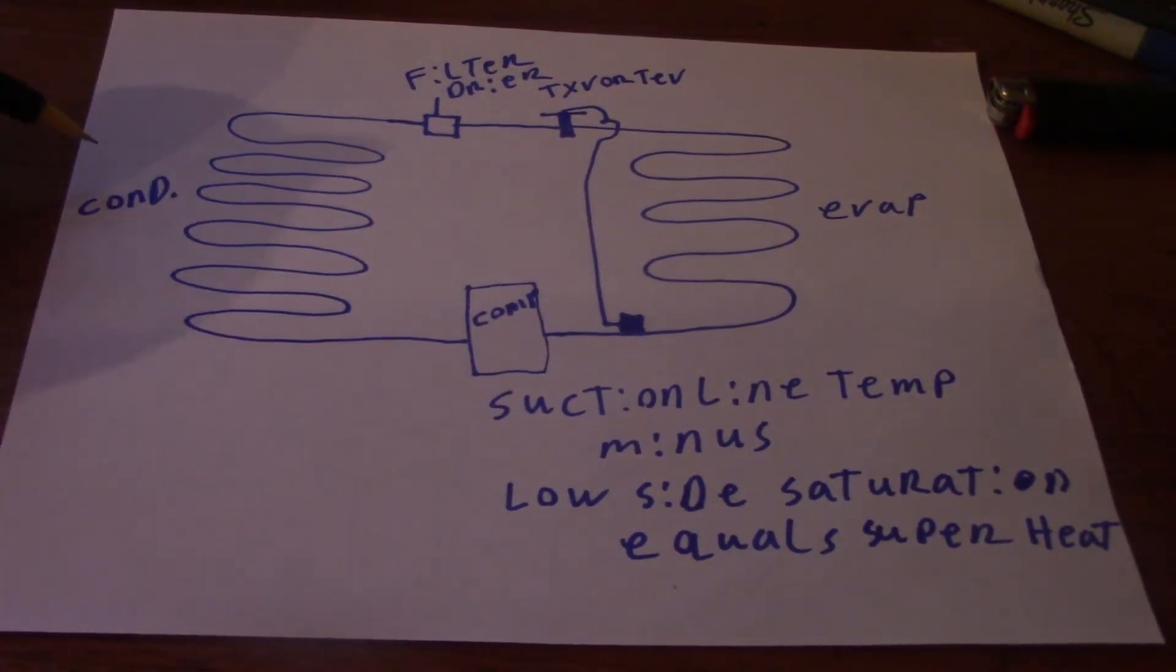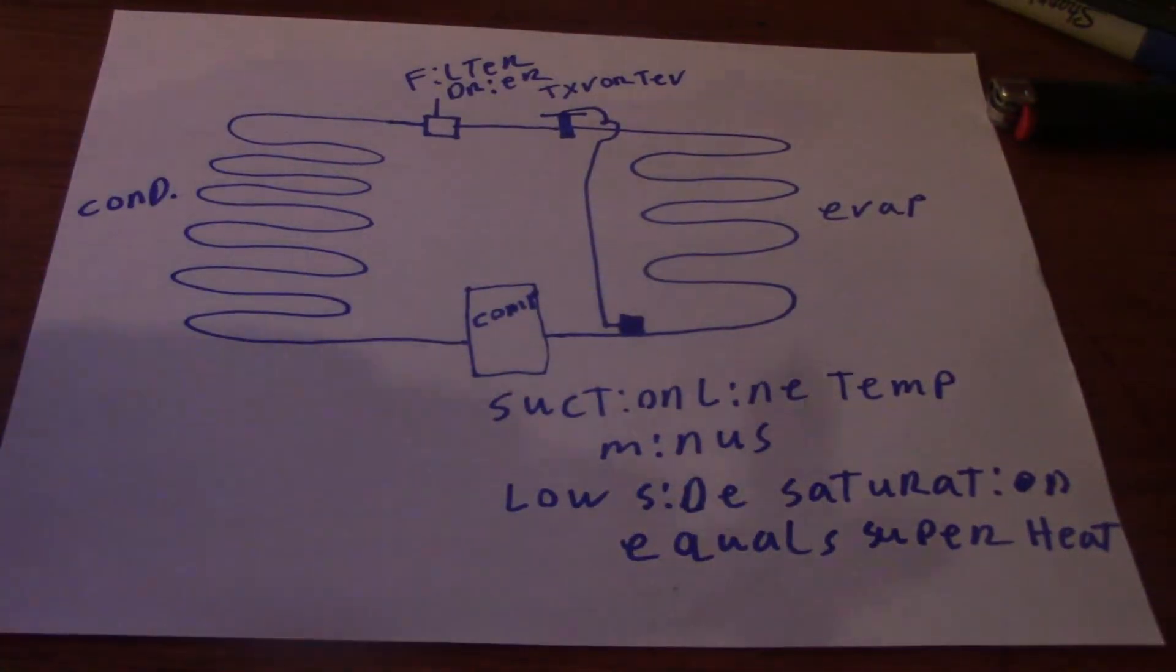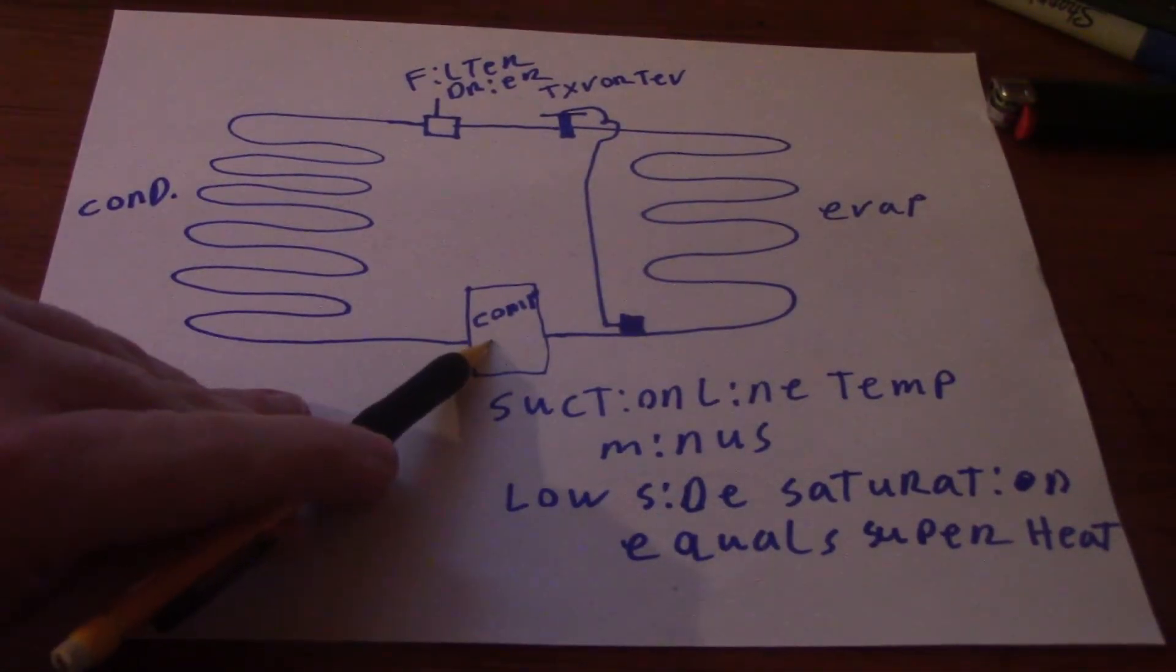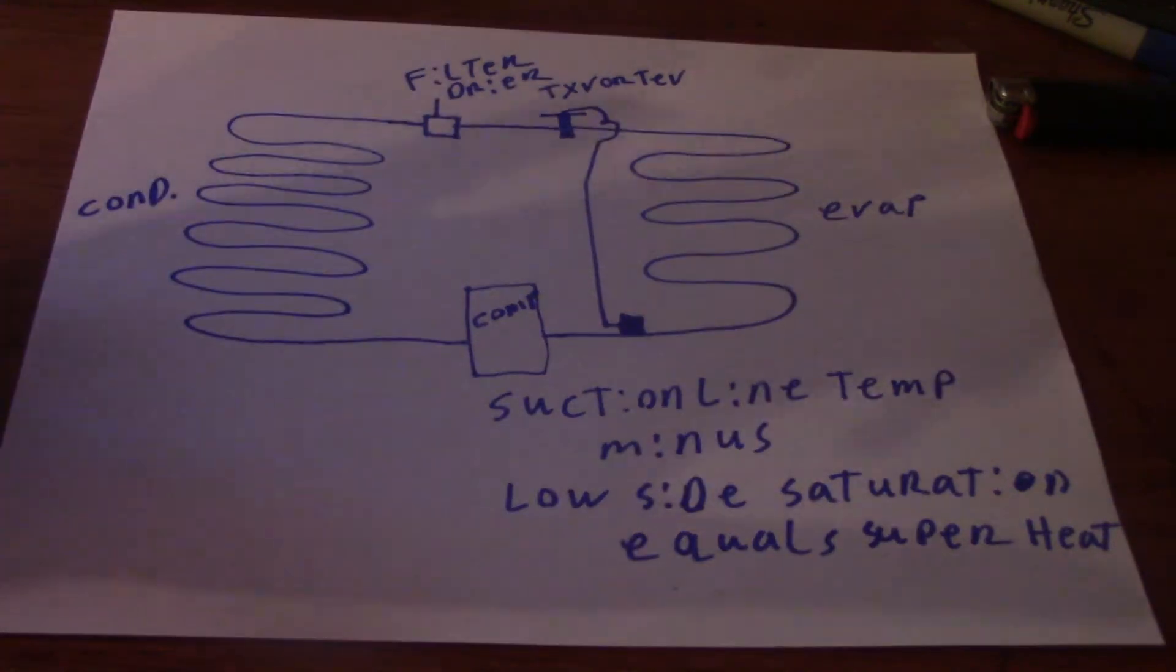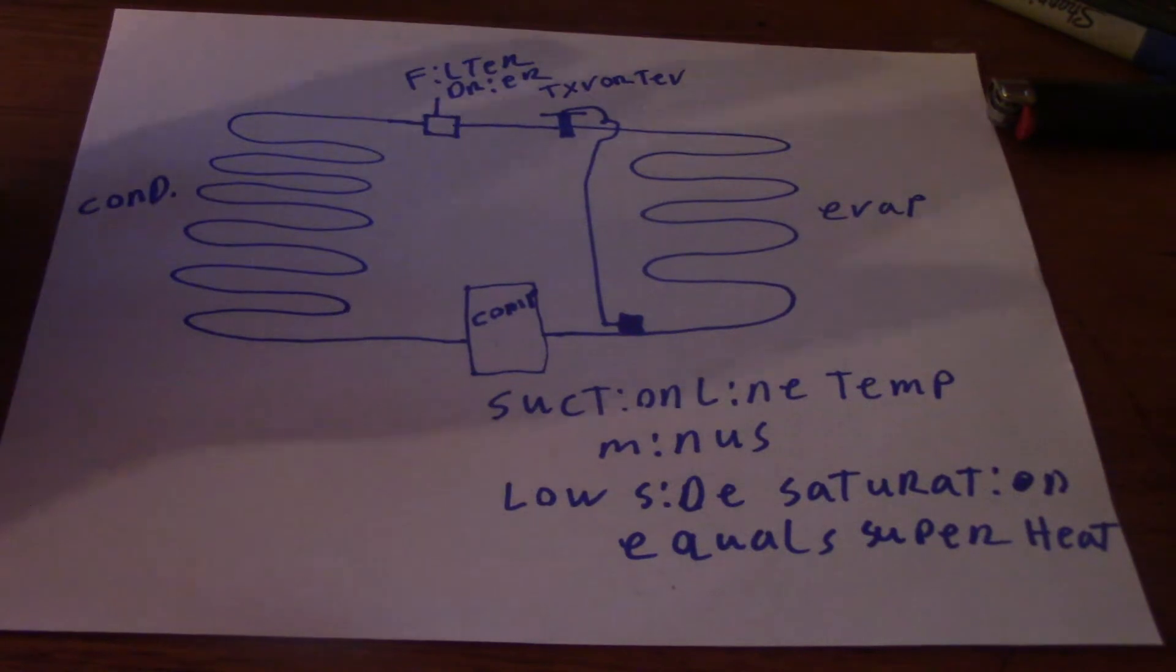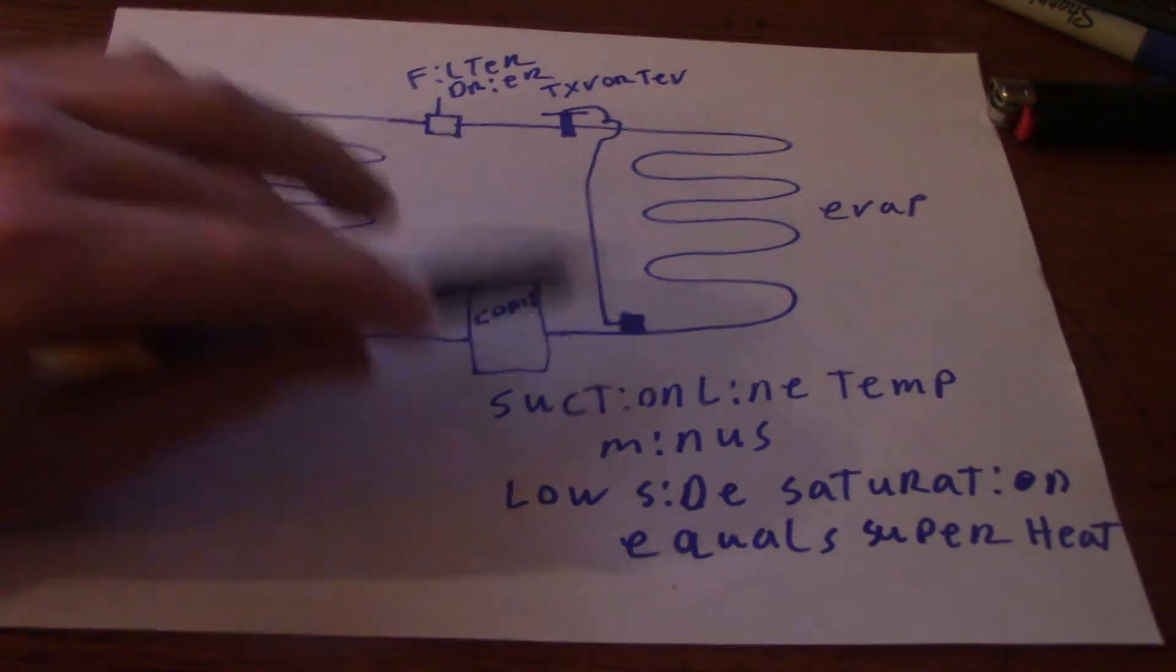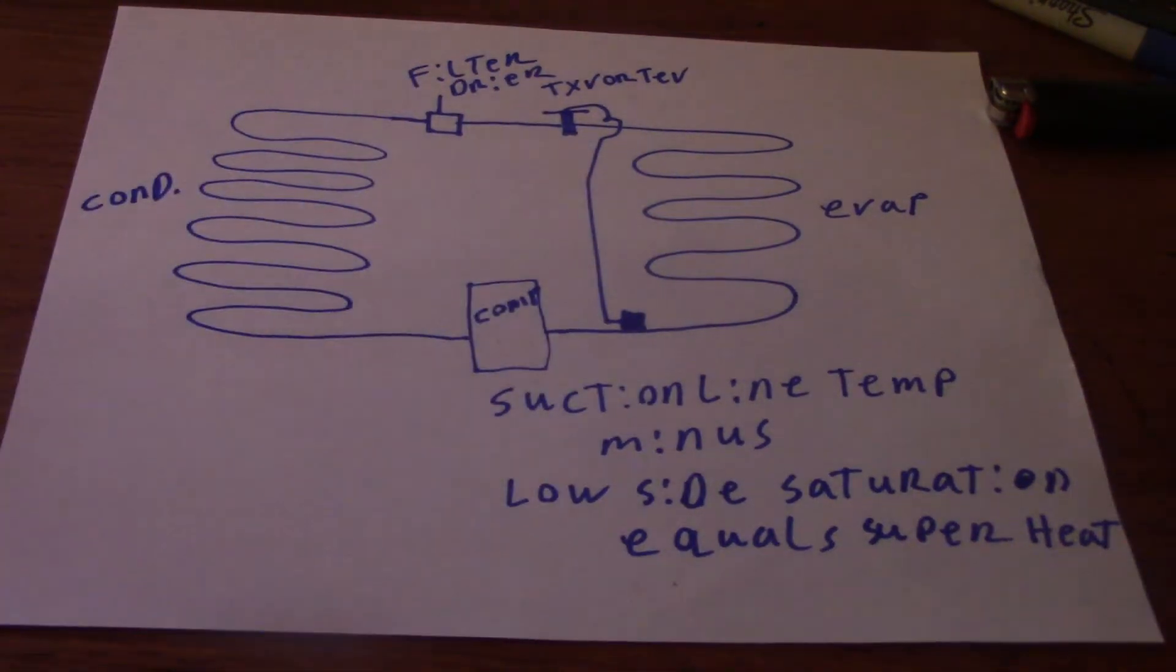We have our high side of the system, which is labeled there with cond, which would be the condenser. Evap is on the low side of the system. Your compressor is the heart of it. I drew this out very basic, where you have a filter dryer and a TXV or TEV depending if it's Parker or Sporlan. Your filter dryer is always before the TXV. Sensing bulb goes on the suction line and the outlet of the evaporator.